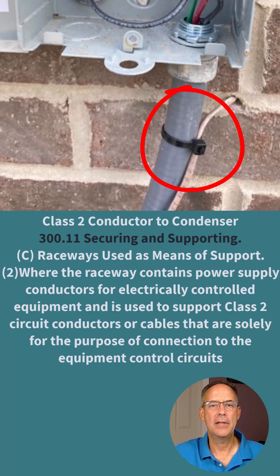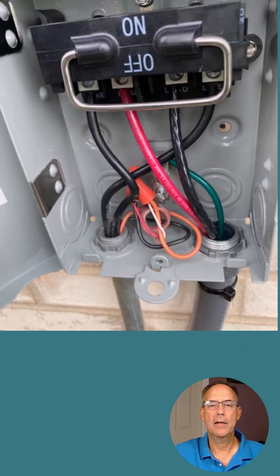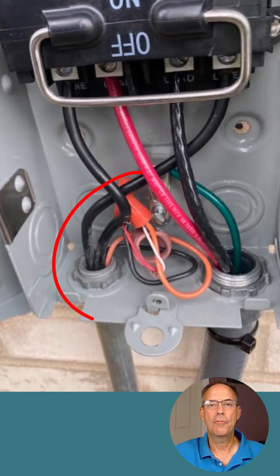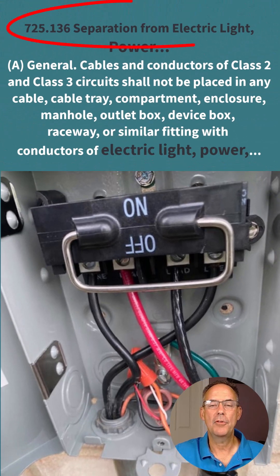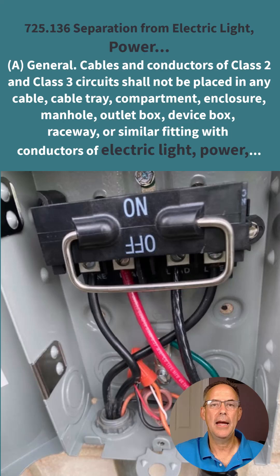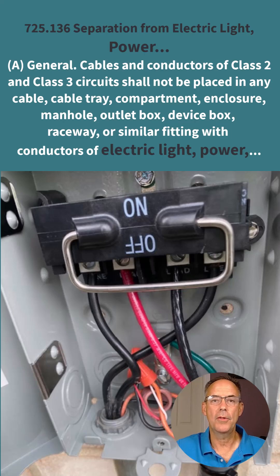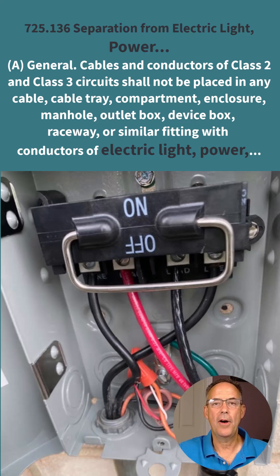The Class 2 conductor that goes from the furnace to the contactor and the AC condenser — as seen in this photo — can be run and strapped to the seal-tight conduit going to the unit itself. A common violation is running that Class 2 wire with the power conductors. If you look at 725.136 of the NEC, it tells you that you cannot run Class 2 conductors with power conductors. You have to follow the separation requirements or not run it with them at all.